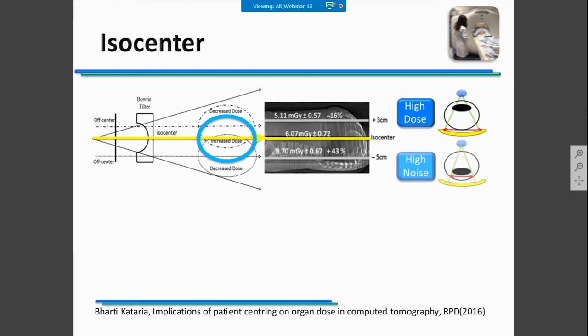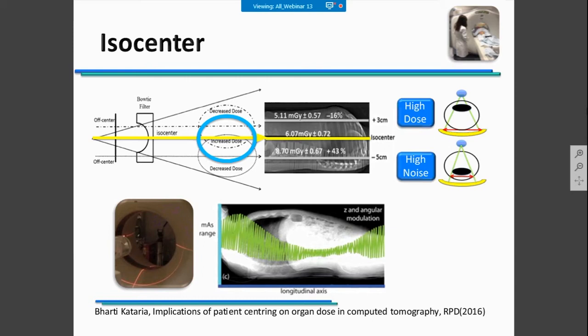For example, the ISO center. ISO center positioning is quite obvious—of course, you need to put the patient at the center of the gantry. However, sometimes it doesn't happen, and you could have high dose values or high noise because the patient is not properly positioned. It's important to say that this is the first step: positioning the patient correctly at the ISO center of the gantry. Also, if you are using a modulation system, it will work properly only if the patient is at the ISO center.